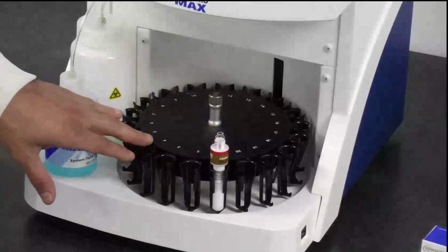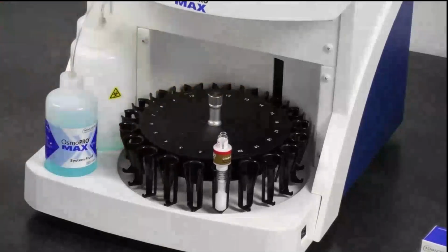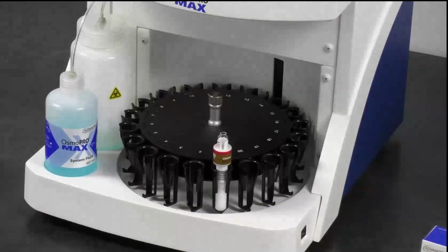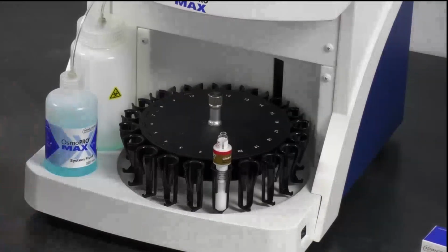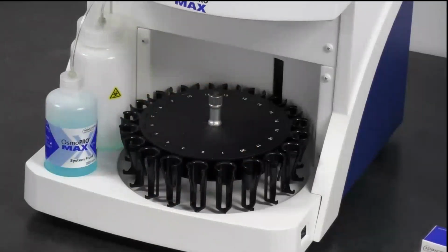You can see the 20 positions, and then this little black rectangle in the back is our onboard scanner. So that's actually what's going to scan each of the tubes as they pass by that I load on. So that's exactly what I'm going to do next. I'm going to go ahead and remove my 290, and I'm going to load some, quote, patient sample tubes, unquote, which is some old water that I've had sitting around here in the demo room for quite some time. That will probably have, maybe, because it's been sitting around for a while, a little bit of osmolality.